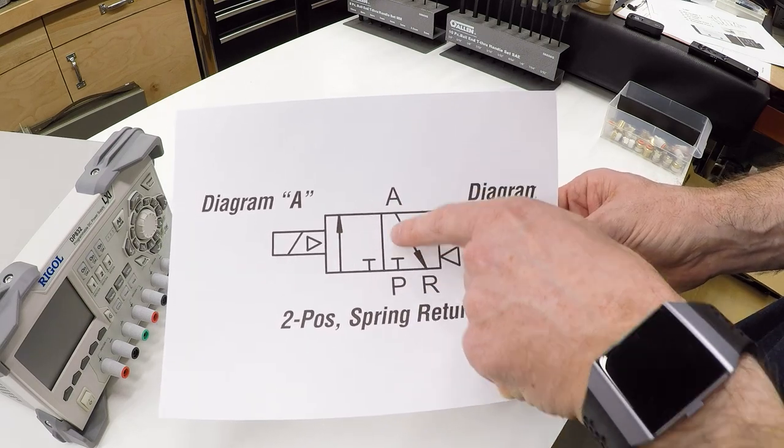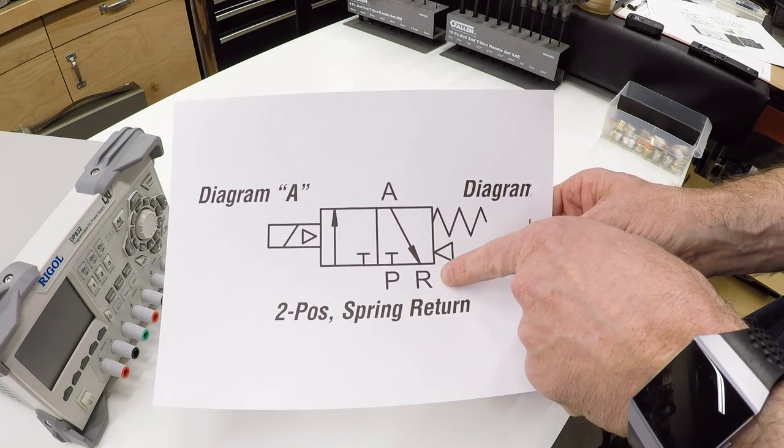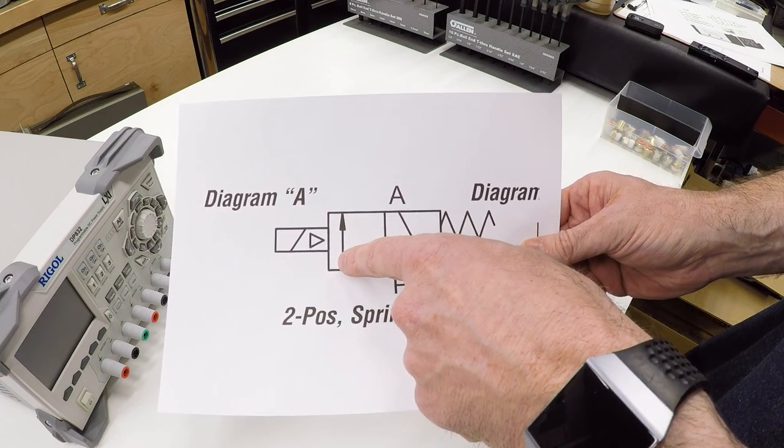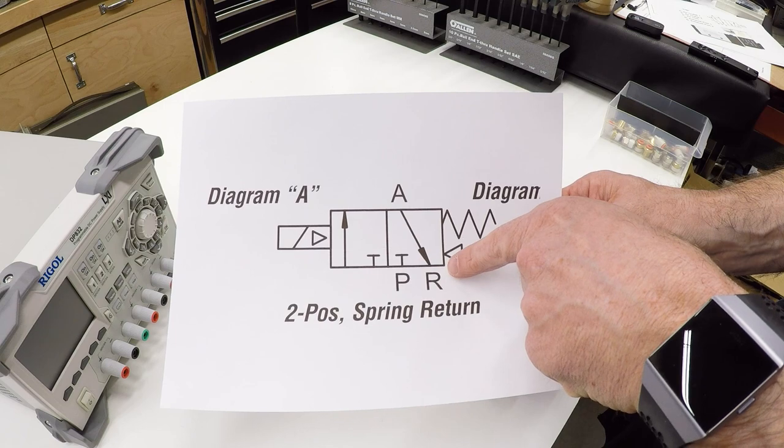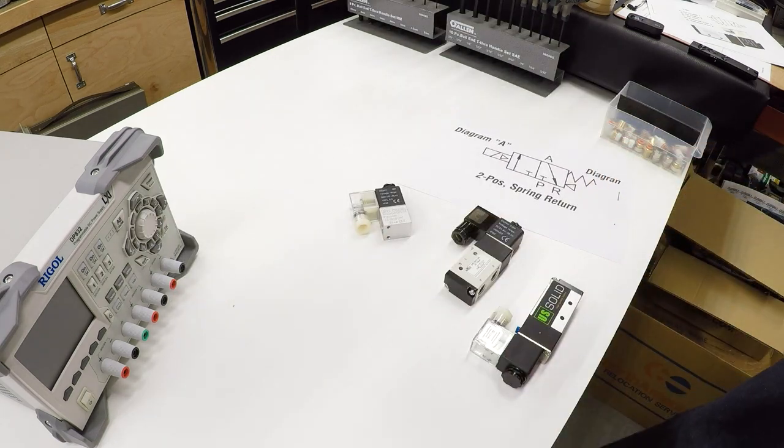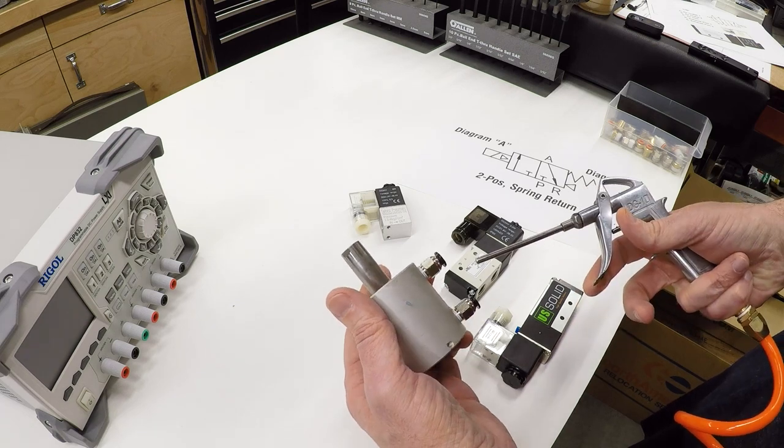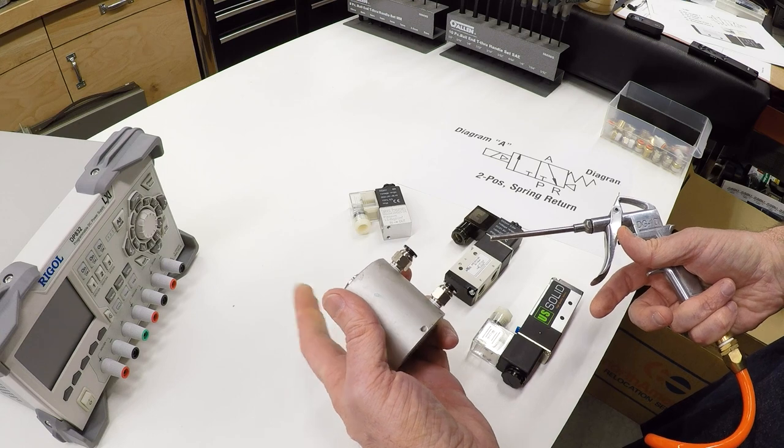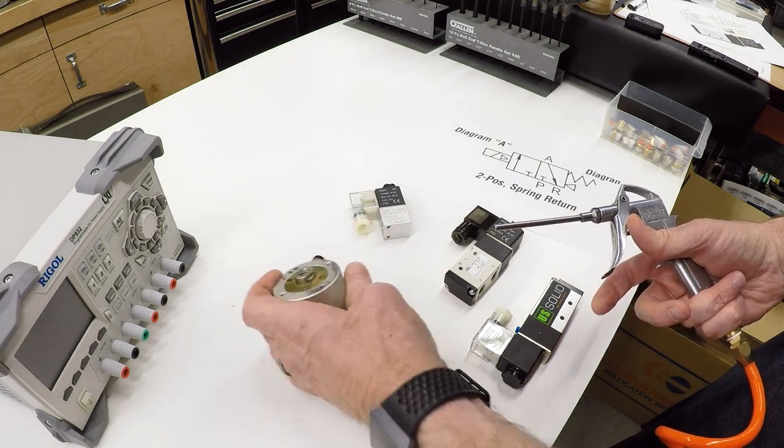When you turn off the magnet, it returns, because of the spring, to this state. The difference is, instead of just blocking the A port, the A port is connected to R, which is the exhaust port. So in this case, you turn it on, it extends the cylinder, you turn it off, and it allows the air to escape from the cylinder out the exhaust so that it can retract. It extends, and then when you release the pressure, it opens this port back up, connects it to the exhaust, and the cylinder can be pushed back by a spring.